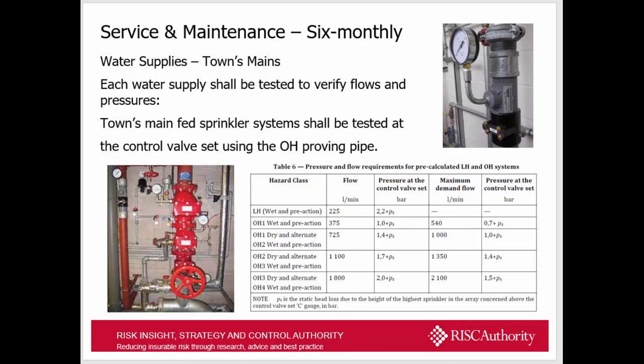Still on six-monthly requirements: if you have a town's mains water supply without a pump and tank, you are required to check the flow and pressure being supplied using a proving pipe. You read the gauge as you check the flow and pressure on the town's mains and verify the various flows and pressure requirements covered in Table 6. For different hazard classifications, there are different pressure and flow requirements. If you have a pump and tank, pressure tank, or duplicate pumps, you also need to do a flow and pressure test to ensure correct flow and pressure is being supplied to the fire area.